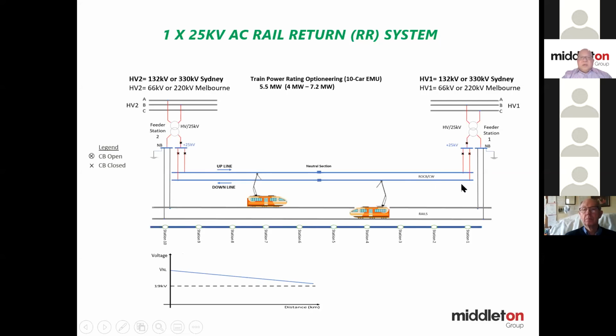So 25 kilometers long. And if you're using a rail return system, and if the train is rated at 5.5 megawatts, it is very unlikely that you can feed from one end to the other. So you may need to use 2 feeding points to feed into the tunnel and have a neutral section between them. Why do we have a neutral section? Because we can't always guarantee that we're taking from the same phases. Here on the left-hand side, I've shown that you're taking supply from A phase and B phase. On the other side, I'm taking B phase and C phase. So if we don't have a neutral section, it would go bang here. So that's why we need a neutral section, which is a dead section to segregate them.